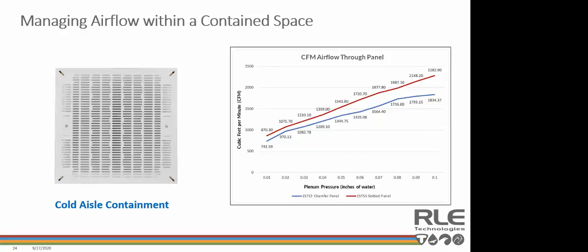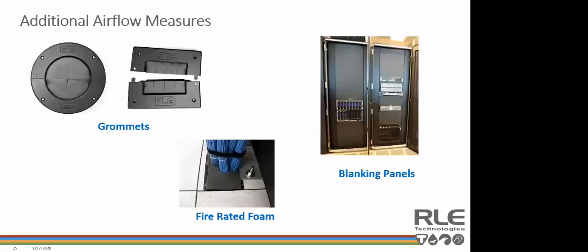Now I'll hand it to Tom, who's going to talk about additional airflow measures and additional things you can do to prevent leakage. Thank you, James. In addition to aisle containment, don't forget about the other areas that compromise airflow. Plugging holes is one of the easiest ways to improve airflow and efficiency in any raised floor environment. This becomes more critical when using aisle containment. If air escapes from the contained aisles through these types of openings, you are limiting the effectiveness of the containment and decreasing your cooling efficiency.